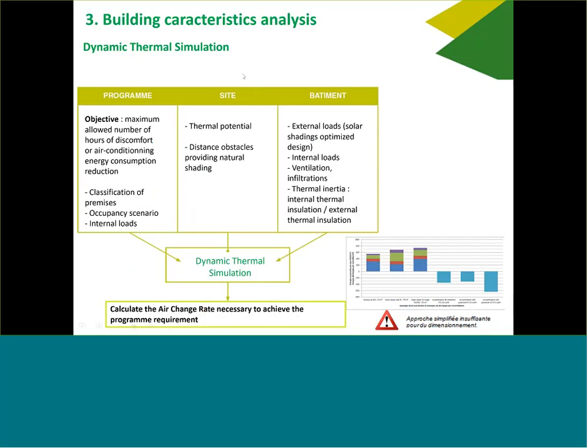What we found is that if you want to size ventilative cooling like an engineer, you need to go through a dynamic thermal simulation. To do your dynamic thermal simulation, you start from your program: what is the number of hours I allow of discomfort, and what is the level — is it 27 or 28 degrees? We highly recommend targeting 28 degrees if the client is okay, because 27 degrees will really increase a lot the number of air changes per hour you will need. In a Mediterranean climate, 28 is much more manageable. In continental climate it could be very different — in some cases, one air change per hour is enough. Then you model the type of building: what is the occupancy scenario, all your internal loads, the thermal potential from the site.